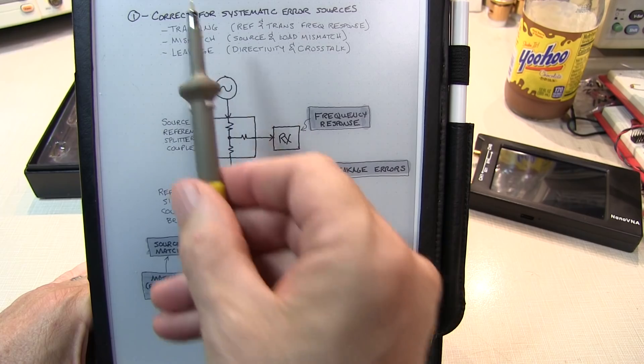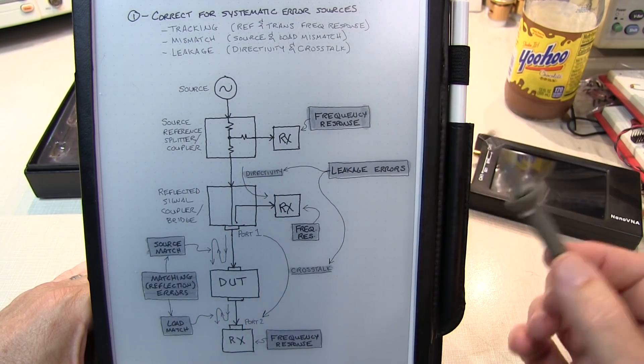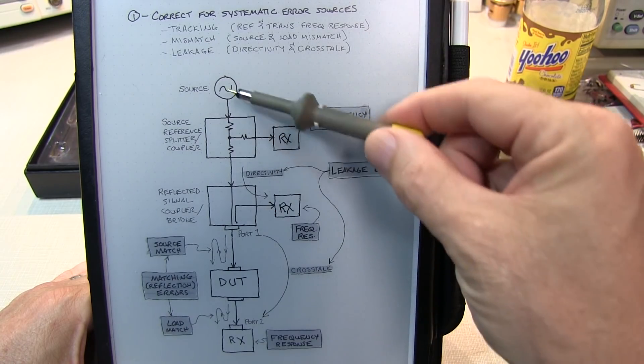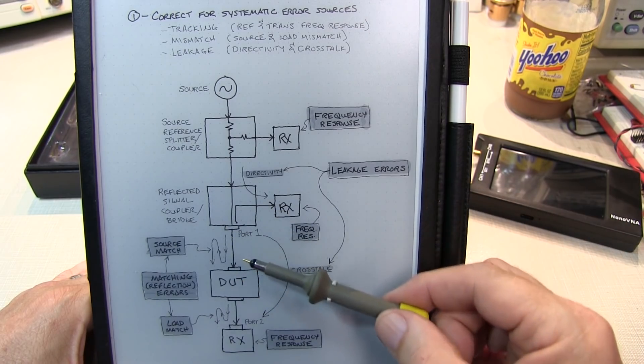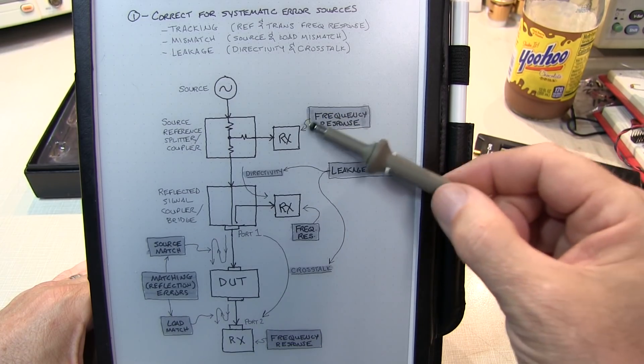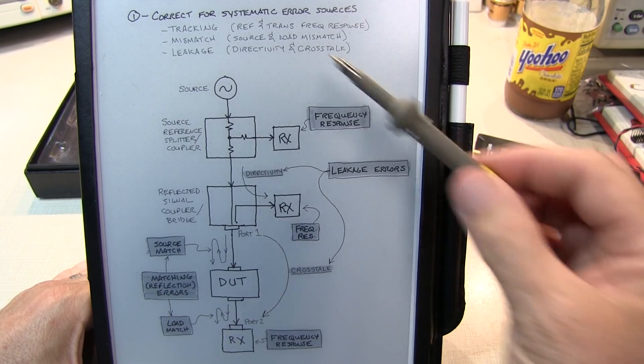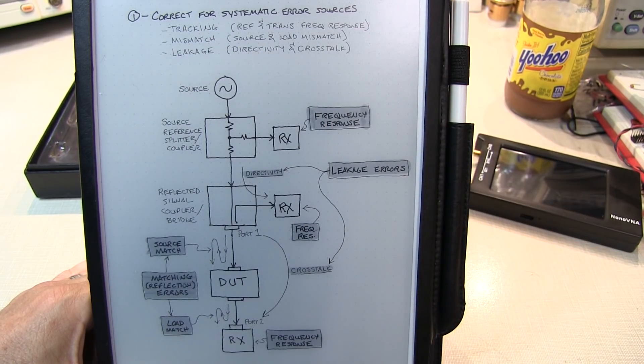What does a user calibration actually do? The first thing is it corrects for what are called systematic error sources. And these are things like what are called tracking errors, and this is a reflection and transmission frequency response. So on the VNA, remember that we've got a source that we're sampling internally, sending through a directional coupler to the device under test that's measuring the reflection coming back, and then we've got a receiver down below that's measuring the through response. So the frequency response of each of these power detectors and the coupler and things like that all have to be corrected for. And those are all part of what is called the tracking and frequency response errors.